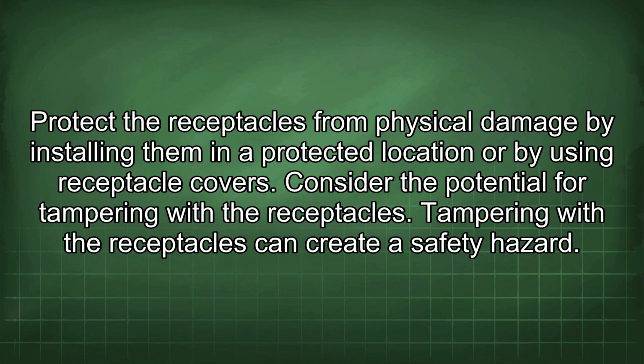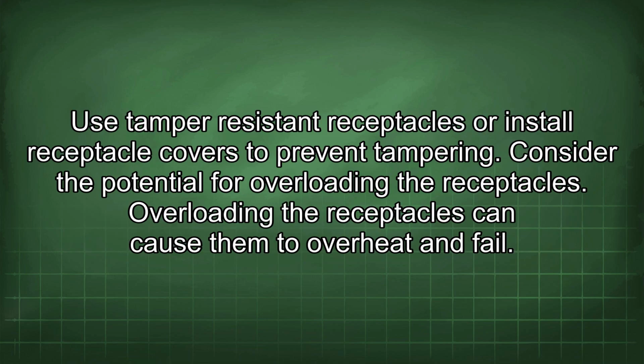Consider the potential for tampering with the receptacles. Tampering with the receptacles can create a safety hazard. Use tamper-resistant receptacles or install receptacle covers to prevent tampering.